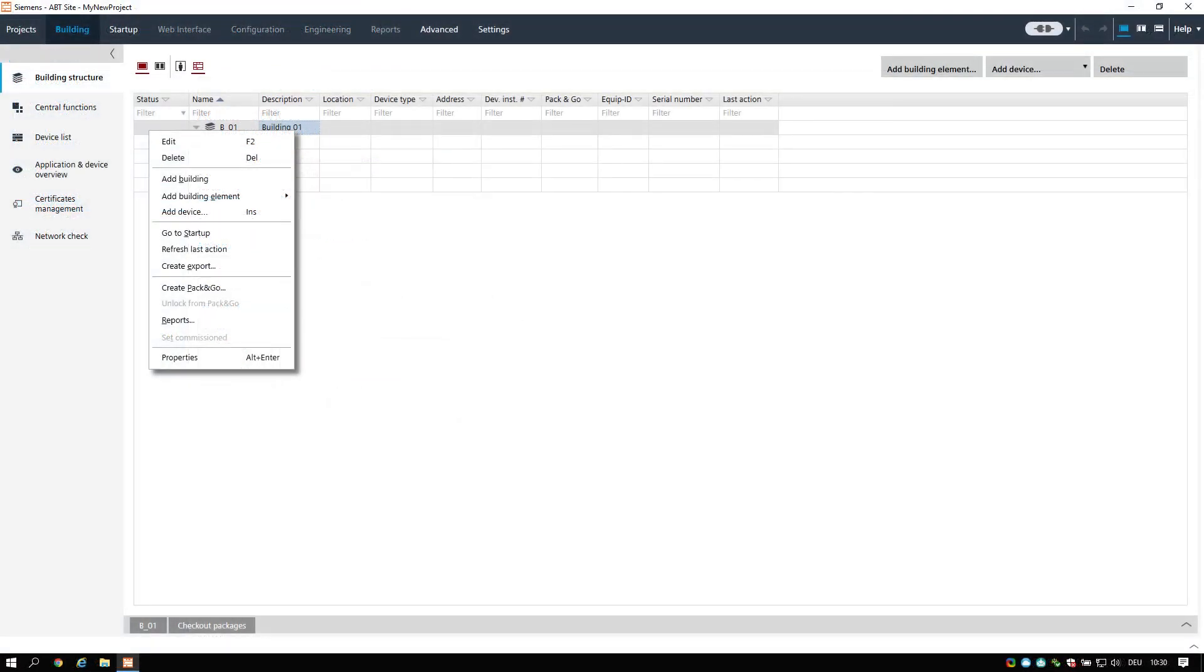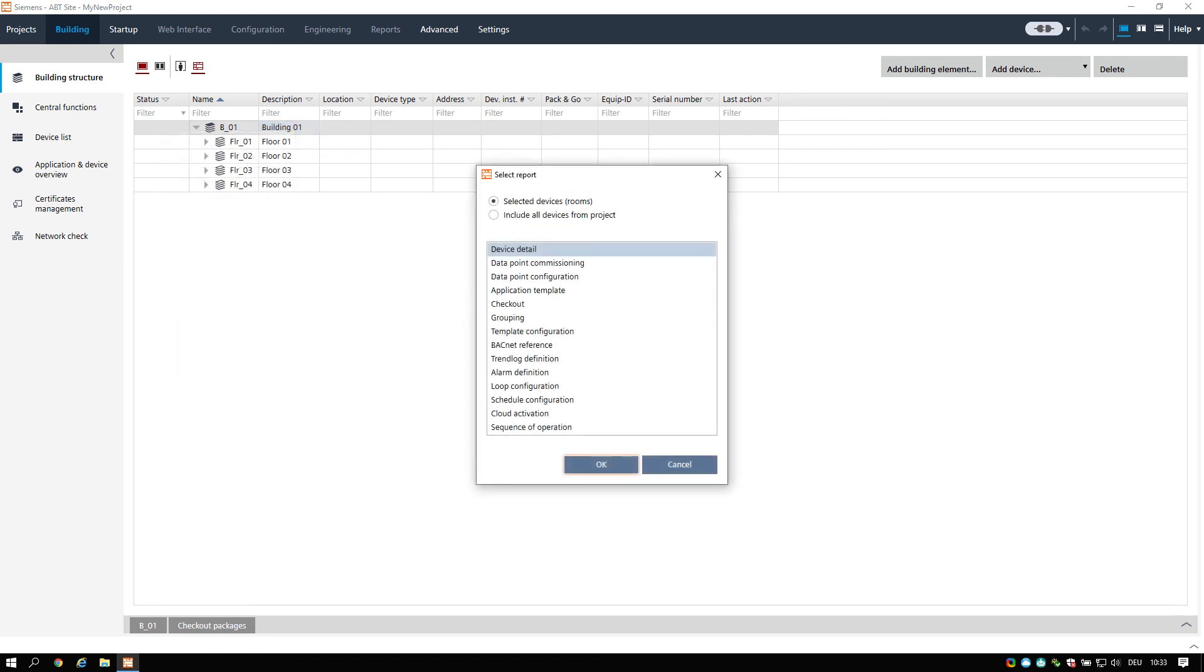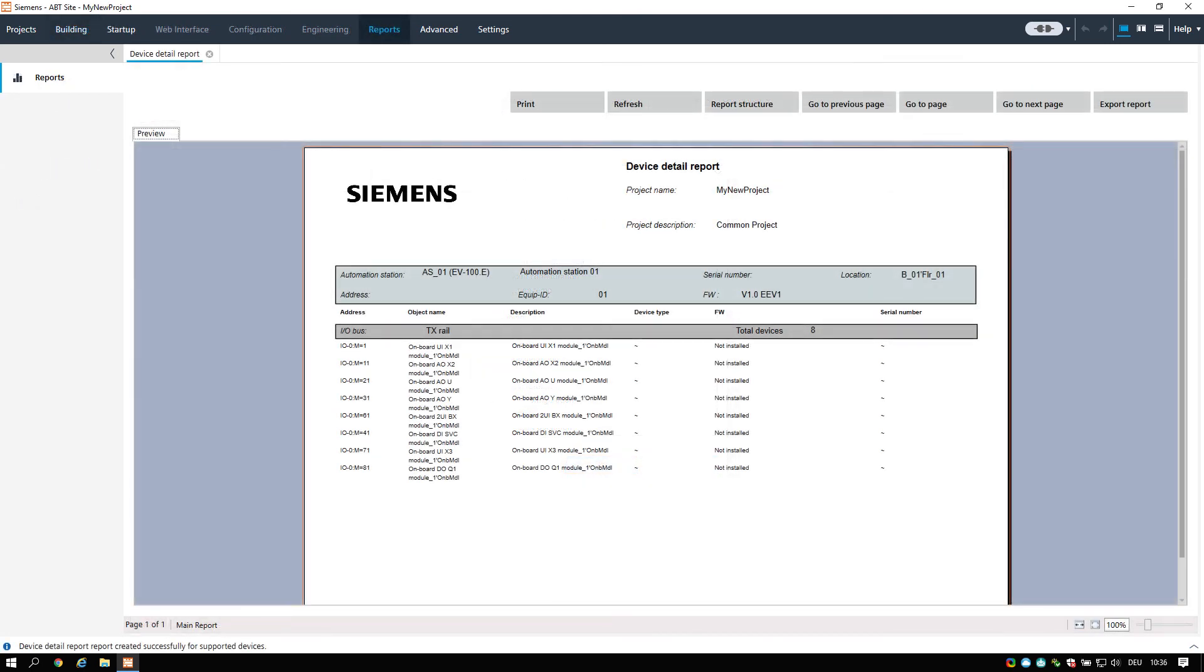Finally we will have a look on two functions which might be required after all engineering and commissioning is done. These are the report function and the data exports functionality. To create a report, select at least one building, building element, device, or hierarchy element. Right-click the selected elements and select create report. In the dialog choose between a single device or all devices in the project. You may preview now the created report.